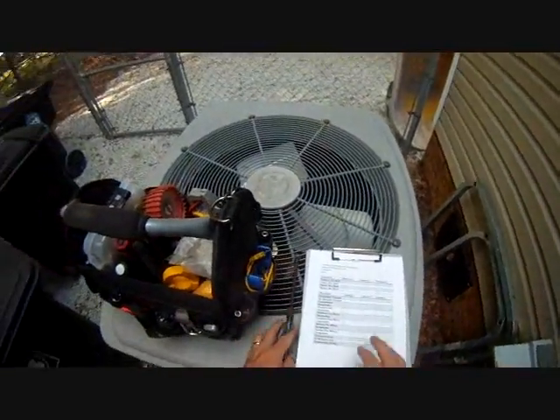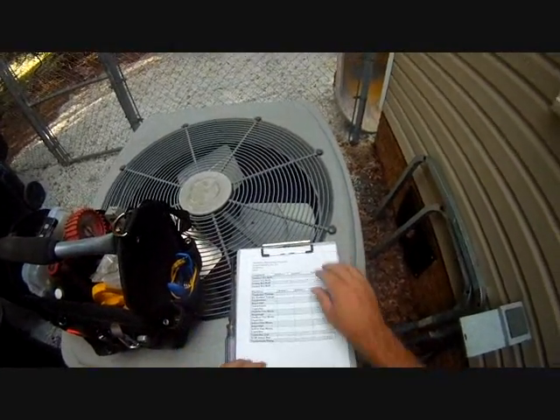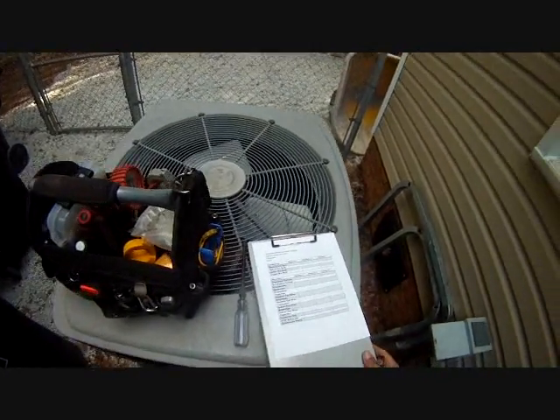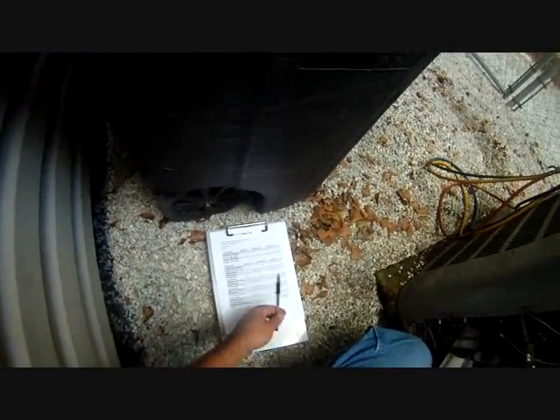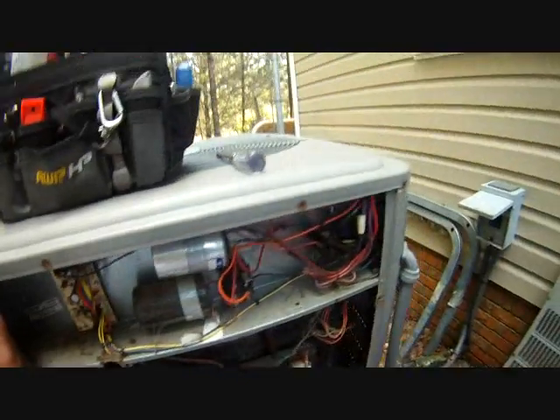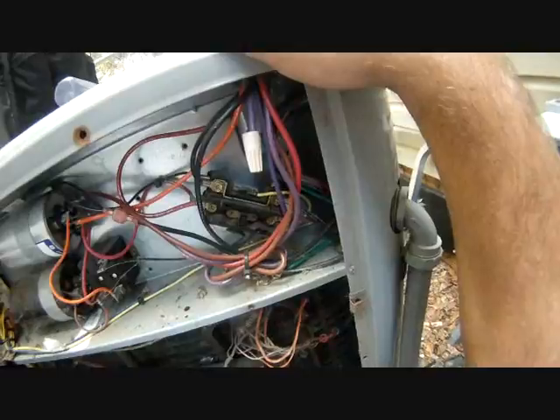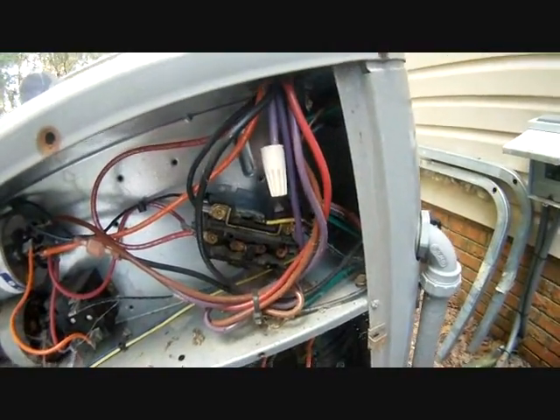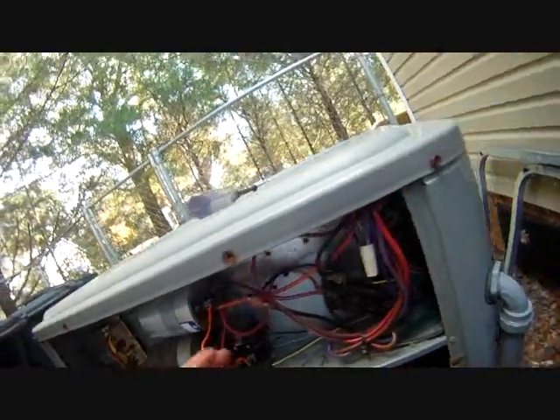I switched from my dry erase form to my write-on form because I have three systems to do, so I have to fill out three different forms anyway. I'll fill out the temperature information whenever I get to the charging part. Right now I'm going to be doing the contactor, which looks kind of rough — might end up getting a new contactor. All the pitting inside looks pretty bad. But first we'll be doing the run capacitor.